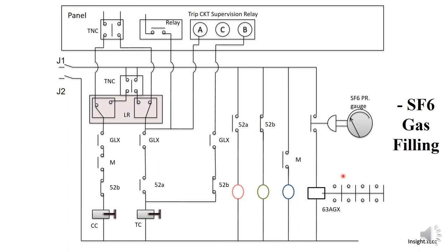This contactor is operated whenever gas is filled inside the circuit breaker and also whenever it has DC supply. There are a few contacts of this contactor — we call it 63AGX or GLX contacts — that are used as interlocks for the closing and tripping circuit of the circuit breaker. You can see the LR switch, that is the local and remote switch. We will understand in detail how this operates, but first let us understand the closing circuit of the circuit breaker.